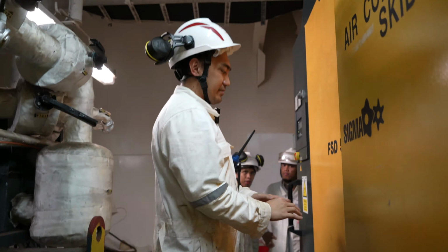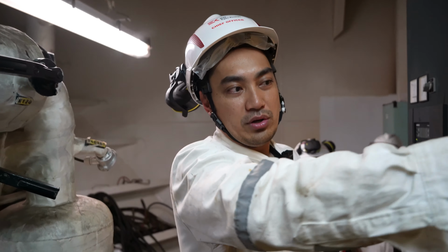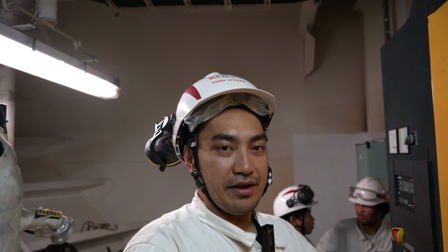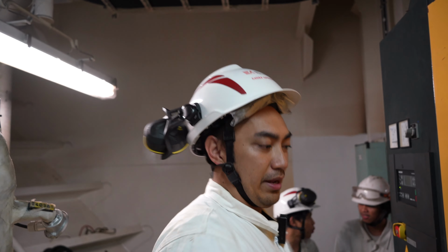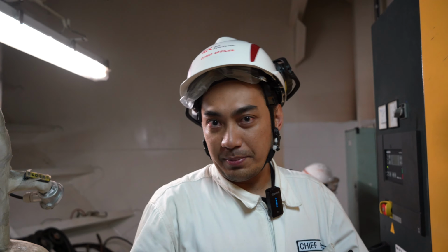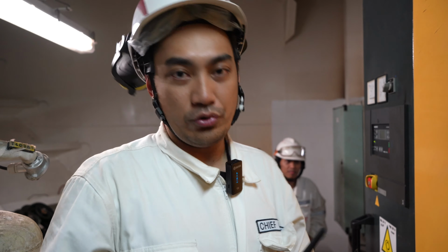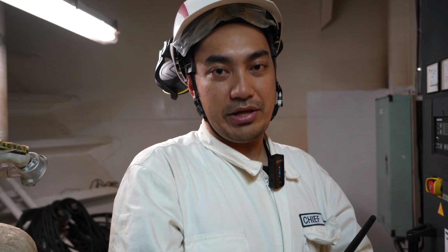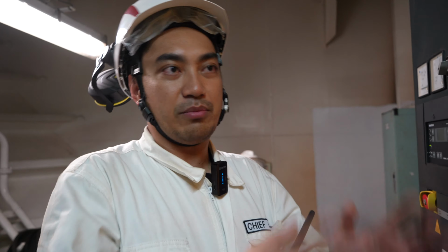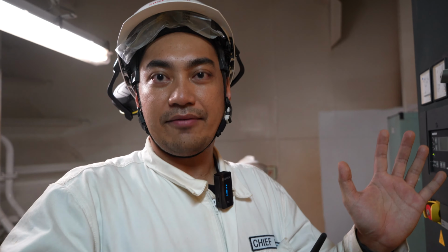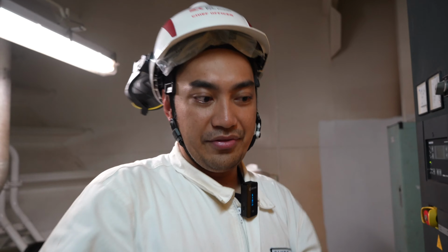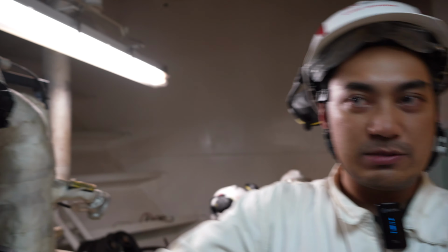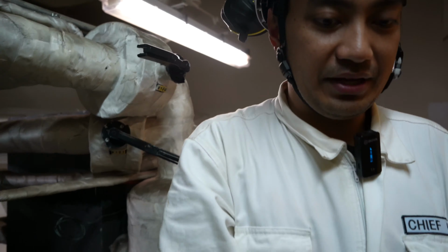Then the compressor will go to coolers. There are air and oil coolers. For the oil coolers, we already know the purpose of it: lubrication and also capacity control. When it comes to air coolers, it is an initial method of the compressor in order to drain excessive water or moisture. And then, when it is being released, before it is passed down to the dryer, you can see a particular vessel here. This is called a cyclone separator.